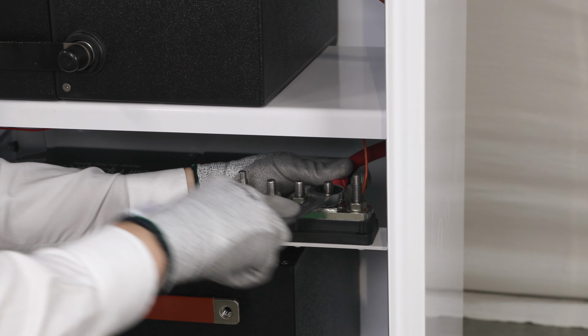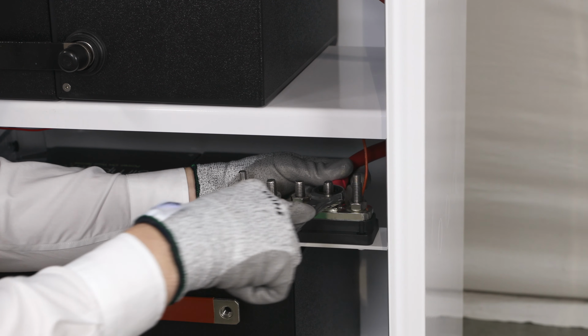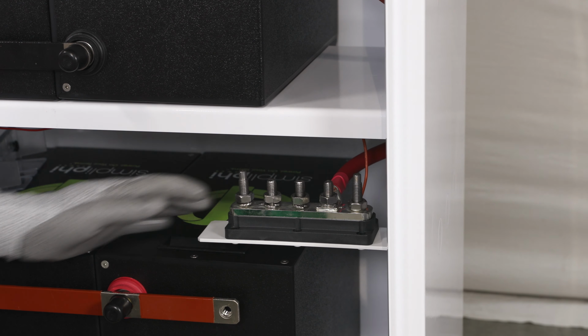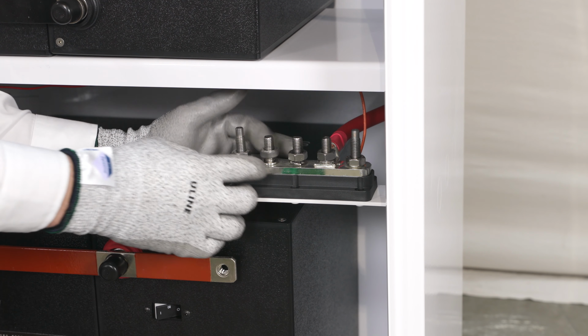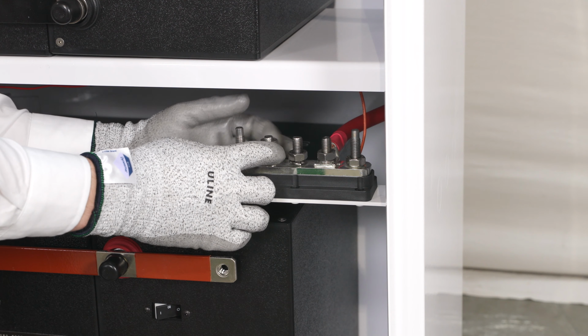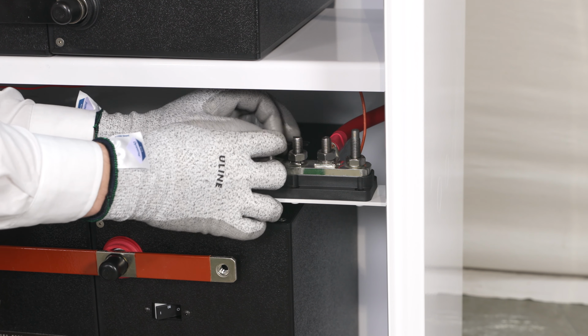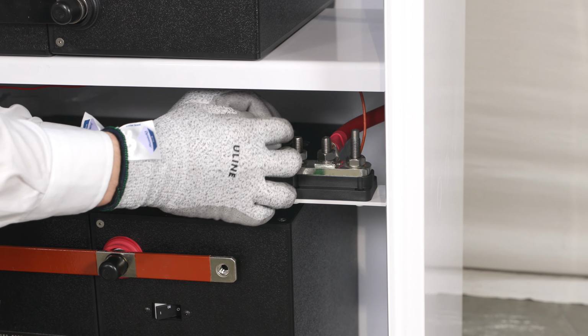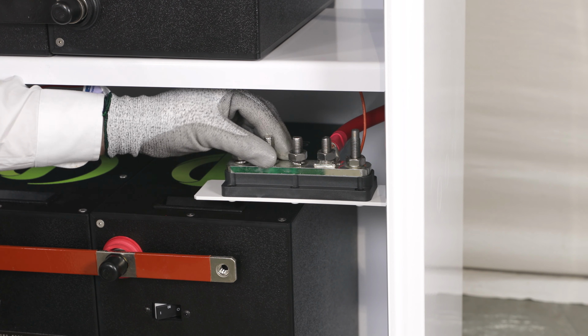You are now ready to secure the bottom positive bus bar to the 5-point terminal block. Remove the nut and lock washer from the 5-point terminal block. We will land the bottom shelf positive bus bar to the terminal block post second in from the left.